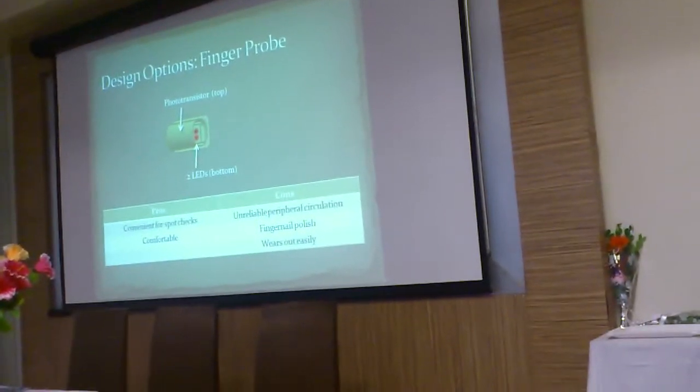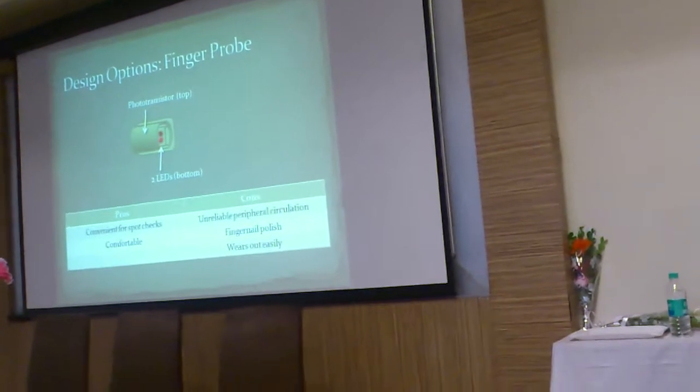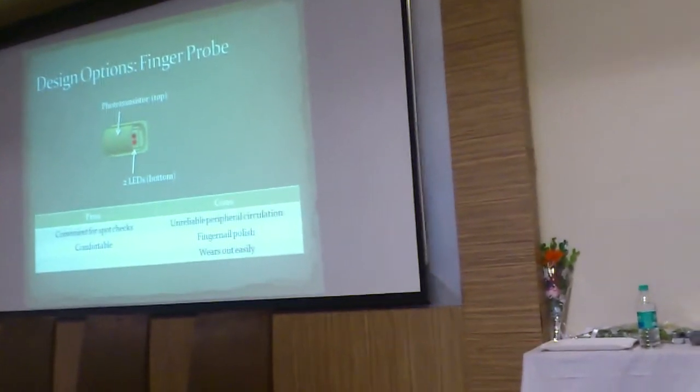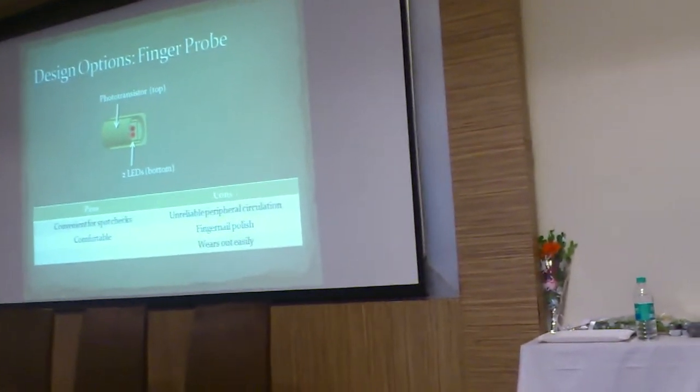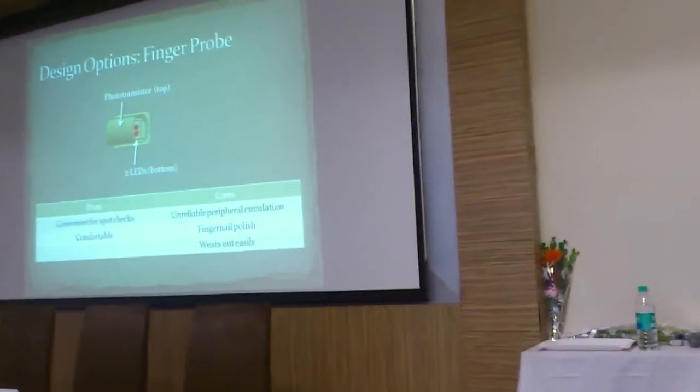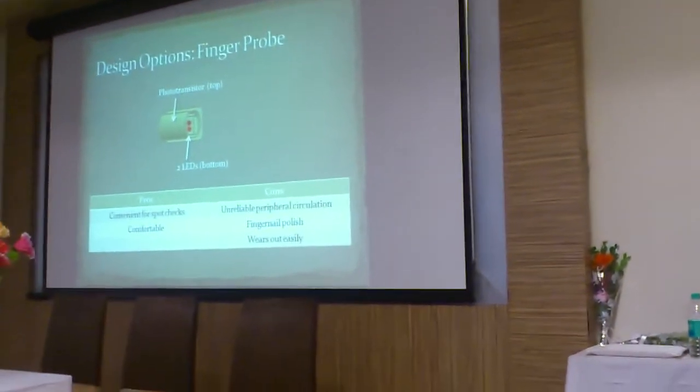This is your two LEDs — red and infrared. Infrared is not visible. The phototransistor is at the bottom and the infrared LED is at the top. You put it like this — two LEDs at the top and a common detector below, which is a silicon photodiode. Pros: convenient for spot checks. Cons: unreliable peripheral circulation, and fingernail polish is a problem. Girls are advised to remove nail polish when hospitalised — they will also cut your nails if they are long, because you cannot put a finger clip sensor on a long nail. And the sensor wears off easily due to scratches on the detector surface.